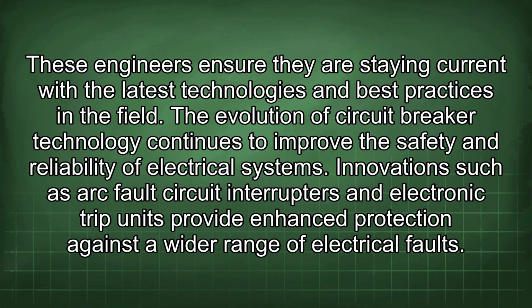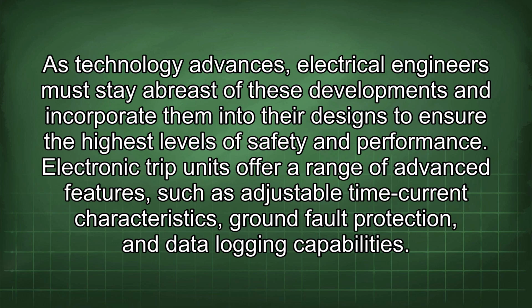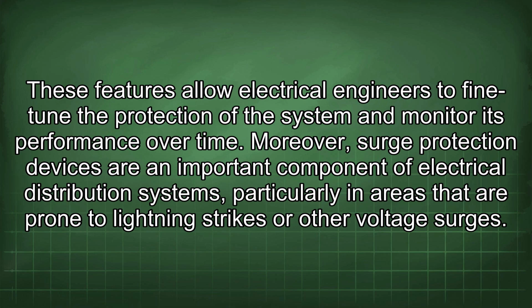The evolution of circuit breaker technology continues to improve the safety and reliability of electrical systems. Innovations such as arc fault circuit interrupters and electronic trip units provide enhanced protection against a wider range of electrical faults. As technology advances, electrical engineers must stay abreast of these developments and incorporate them into their designs to ensure the highest levels of safety and performance. Electronic trip units offer a range of advanced features, such as adjustable time current characteristics, ground fault protection, and data logging capabilities. These features allow electrical engineers to fine-tune the protection of the system and monitor its performance over time.